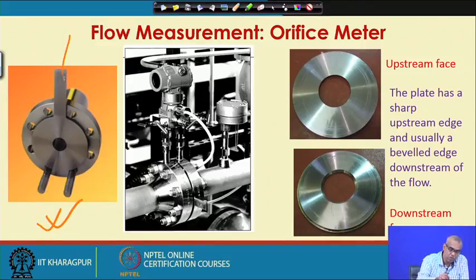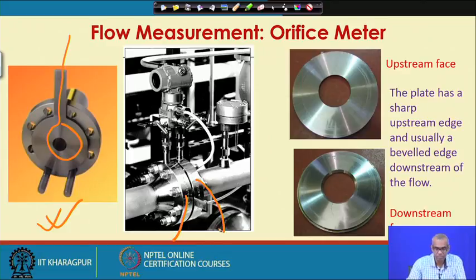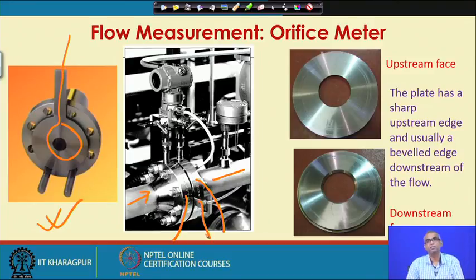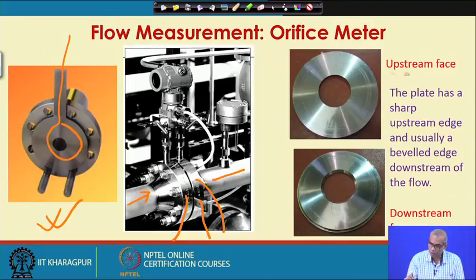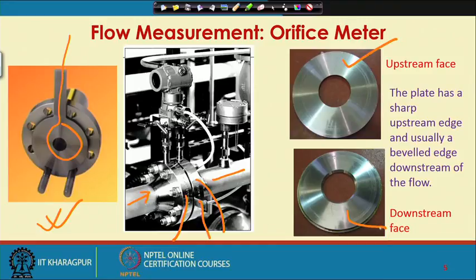This is the orifice plate — you can see the hole. This is the flange, this is the pipeline through which fluid is flowing. The fluid may be flowing in this direction, and this is the orifice plate inserted between the flanges. This is the upstream face of the orifice plate and this is the downstream face. The fluid approaches the upstream face and leaves the downstream face. The plate has a sharp upstream edge and usually a bevel edge downstream.